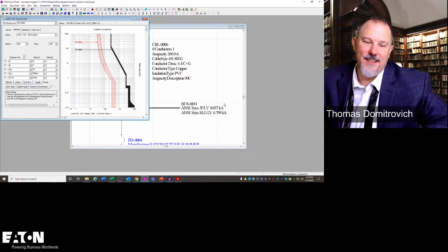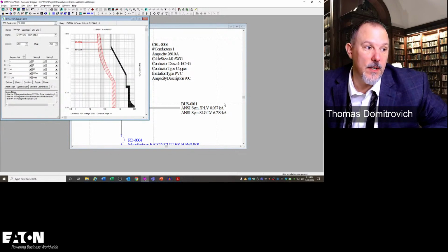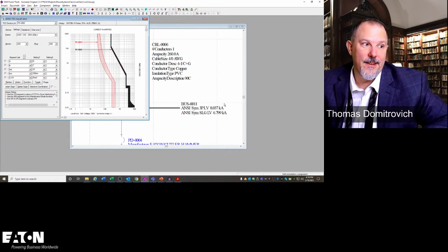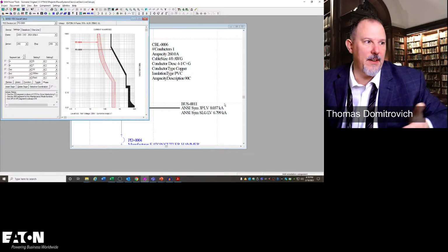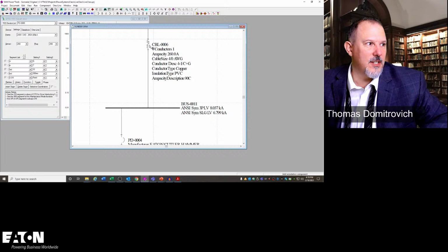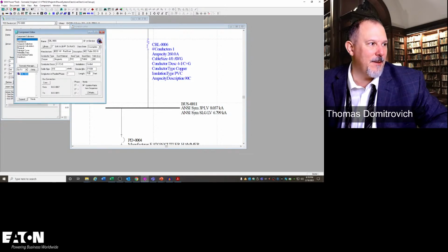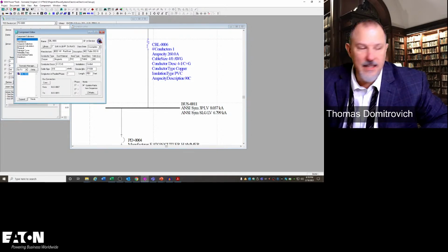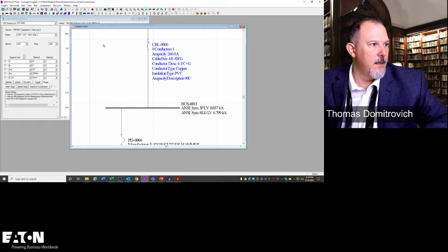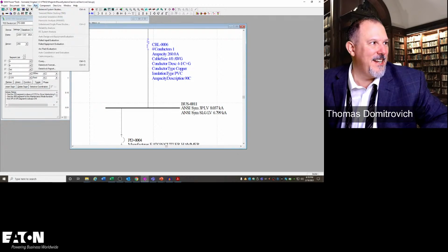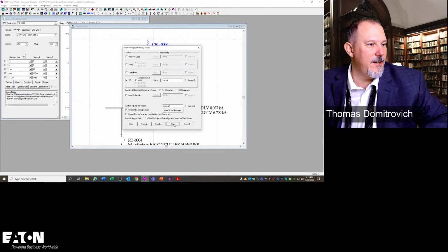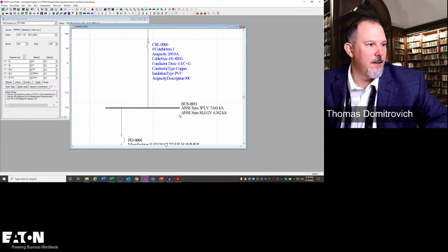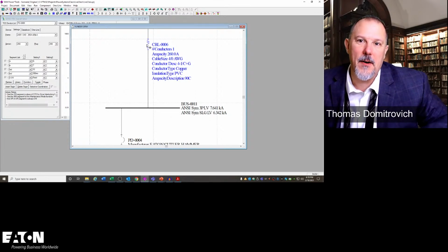8,037. Do I selectively coordinate to 8,000 amps? I'm going to roll it up. I mean, 37 amps. What's 37 amps amongst friends? Is 37 amps a matter of 10 feet? Let's see. Balance study, run. There it is, 10 feet. All I did was add 10 feet of conductor, and now I work.